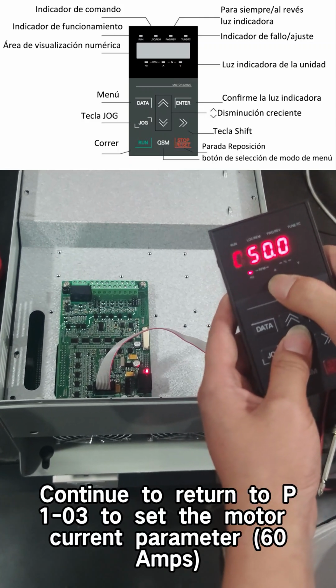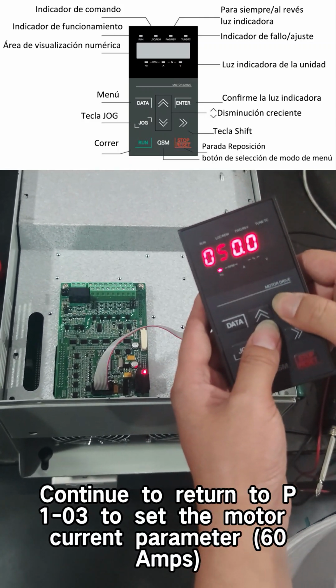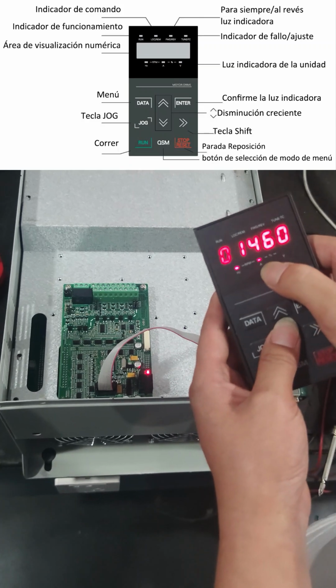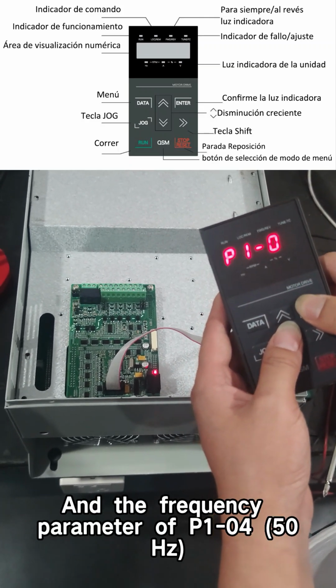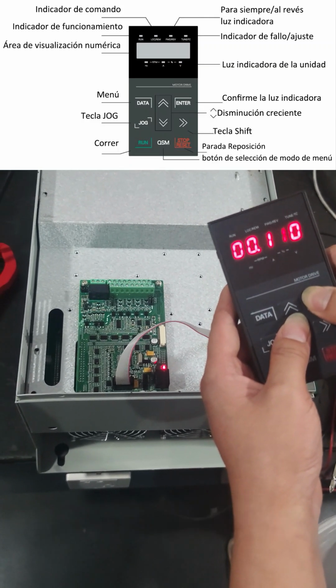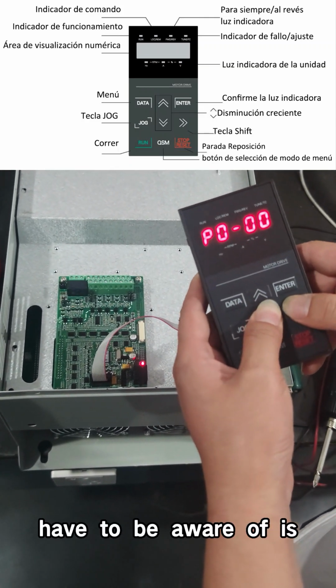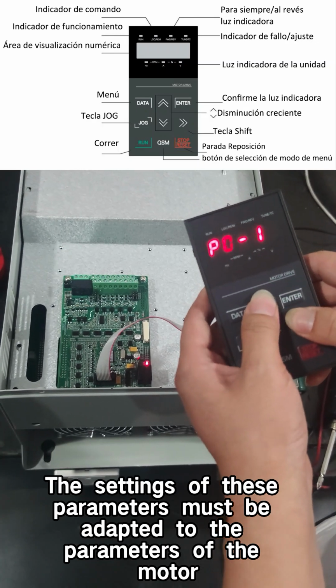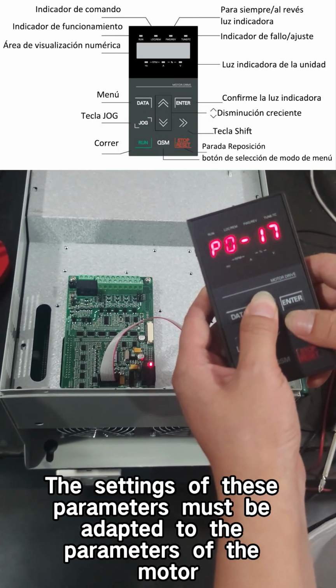Continue to return to P103 to set the motor current parameter, 60 amps. And the frequency parameter of P104, 50 Hz. P105 sets the rated speed of the motor. One thing to be aware of is that the settings of these parameters must be adapted to the parameters of the motor.